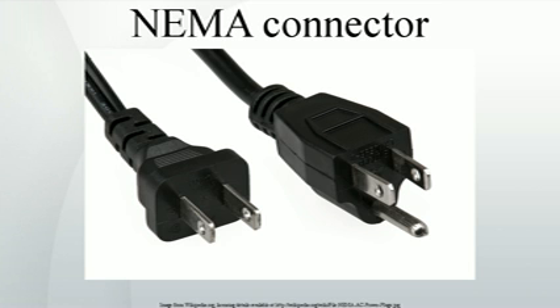The usual orientation in residential buildings is with the ground pin on the bottom, while in commercial or institutional buildings this pin is on top, per National Electrical Installation Standards, NECA 130/2010. Sideways installation is also permitted. In this case, NECA 130/2010 specifies the neutral pin is on top. In 46 of the 50 United States and all of Canada, tamper-resistant sockets are required in new residential construction as of November 2013. These prevent contact by objects like keys or paper clips inserted into the socket.